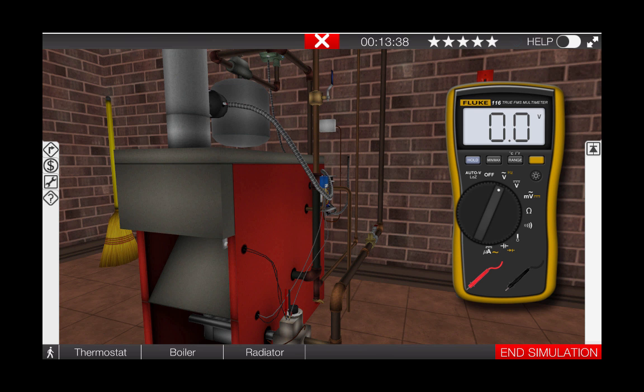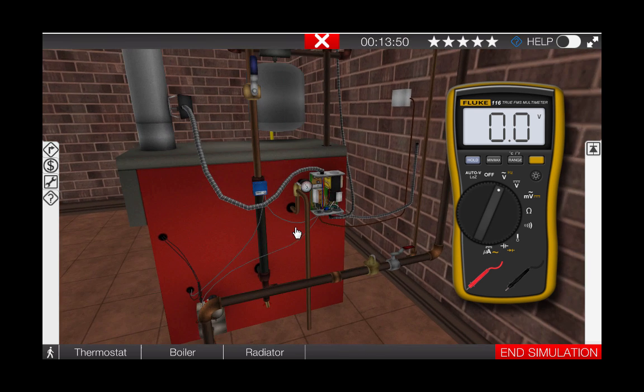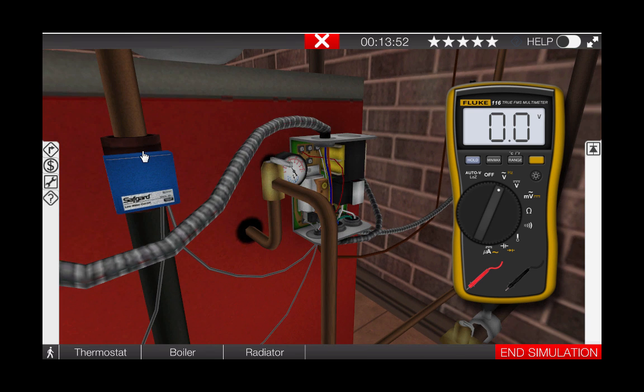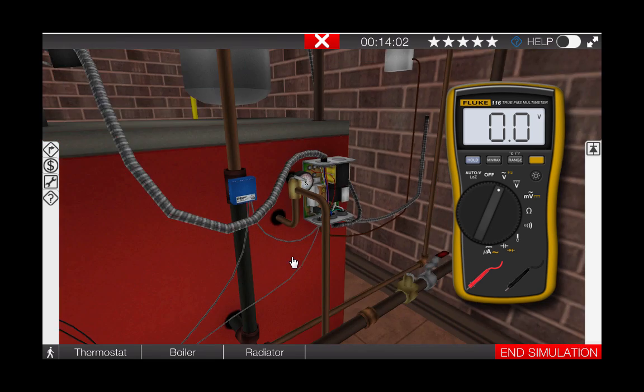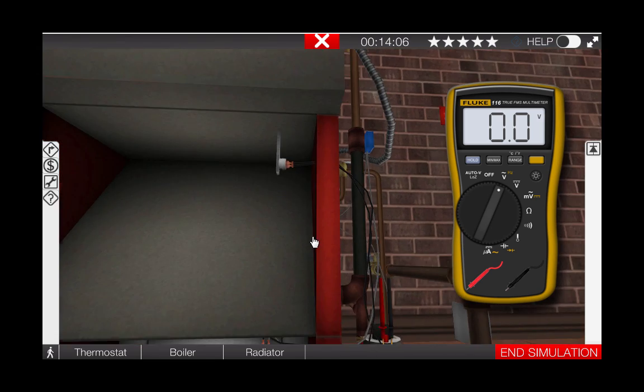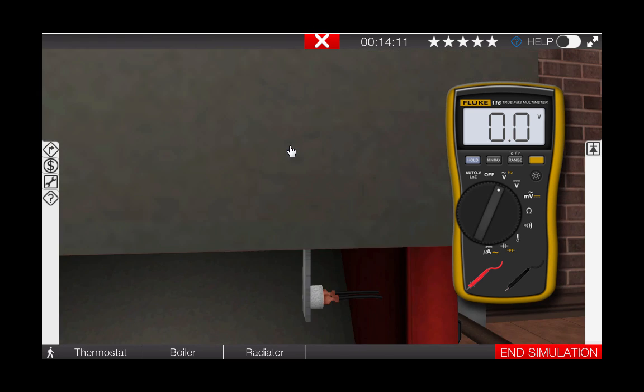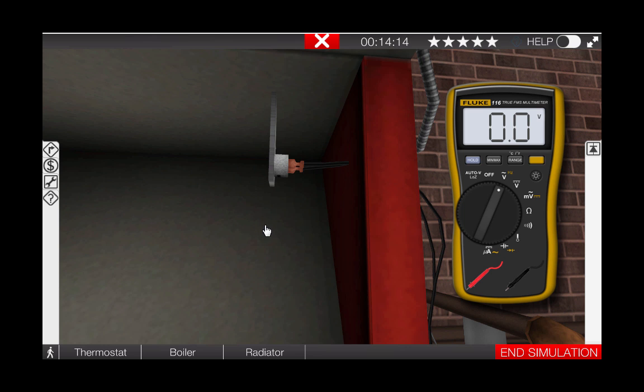Let's check each of the three switches. The first is the low water cutoff, which protects the boiler against a low water condition such as a leak, and will shut the burners off if low water is sensed in the boiler. Our next safety switch is the spill switch, or block vent safety switch. The block vent safety switch is located inside the draft diverter or draft hood of an atmospheric appliance, and protects against conditions such as an obstructed flue or chimney and poor venting design.